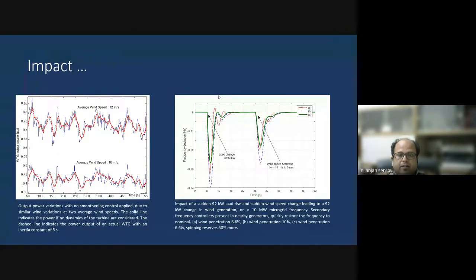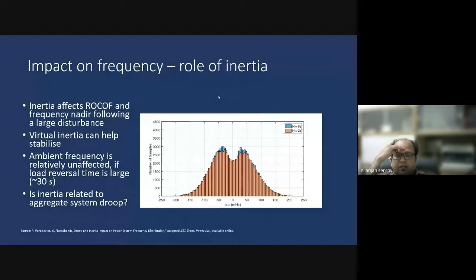In the next slide, recent work has been conducted. In fact, in IIT Delhi also we are working on this. We are looking at the ambient frequency and how it depends on the amount of renewables that have already been injected into the grid. It is found that the ambient frequency is relatively less affected. So how do we look at the ambient frequency? Now we are talking about statistical analysis rather than analysis using differential equation systems. In statistical analysis, we take the ambient frequency and collect a window of data, let's say about 6 to 8 hours of frequency data.